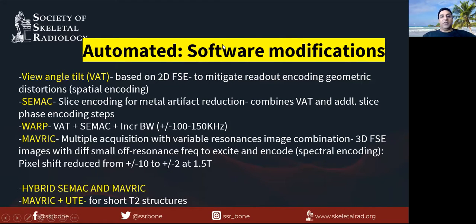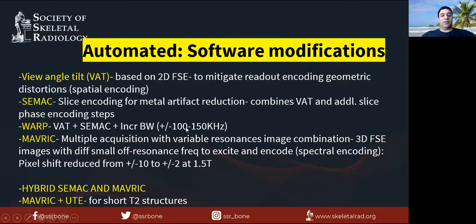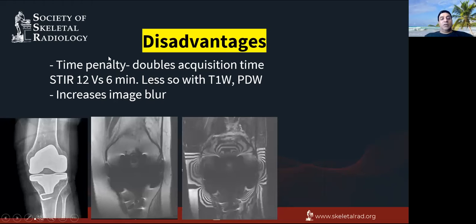There are automated software modifications beyond the manual techniques. View angle tilt mitigates geometric distortions. SEMAC adds phase encoding steps, taking a little more time but reducing distortions. WARP combines view angle tilt and SEMAC while also increasing bandwidth by another 100 to 150 kHz, leading to better imaging. The MAVRIC variant, which is a GE variant, uses 3D fast spin echo images with small off-resonance frequency pulses, reducing pixel shift from 10 kHz to about 2 kHz. These are typically done at 1.5 Tesla, and there are newer hybrid variants as well.